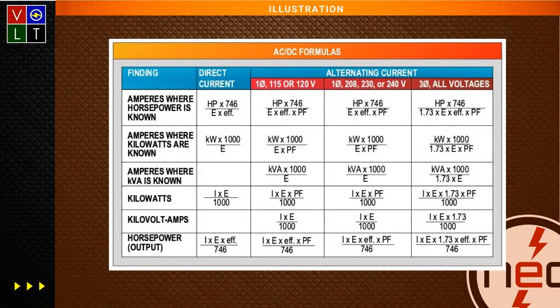Then we show you how to do kilowatts, kilovolt amps, and horsepower, and these are all the different formulas you would use when performing these types of calculations. Is 746 your horsepower rating?